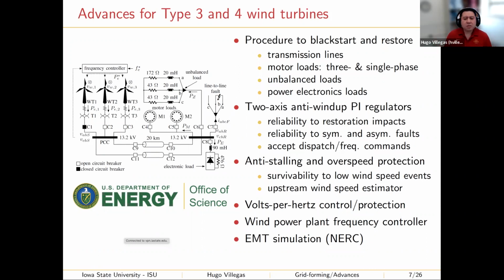And also during the restoration process, it's typically the case that wind turbines have to withstand, for example, unbalanced load, because there is no perfect balancing in the distribution systems. And nowadays, we are also challenged to energize power electronic loads, for example, electric vehicles. Those electric vehicles could be using relatively fast chargers, or other types of chargers, for example type 1 and type 2, which usually withdraw relatively low power from the system.